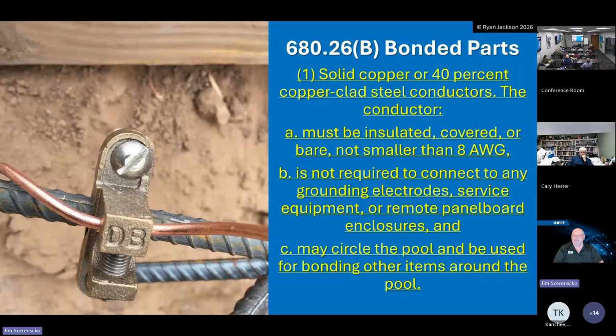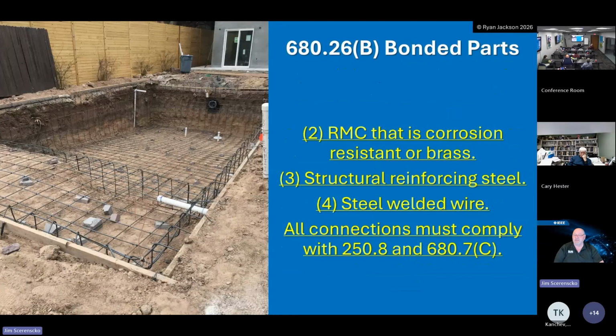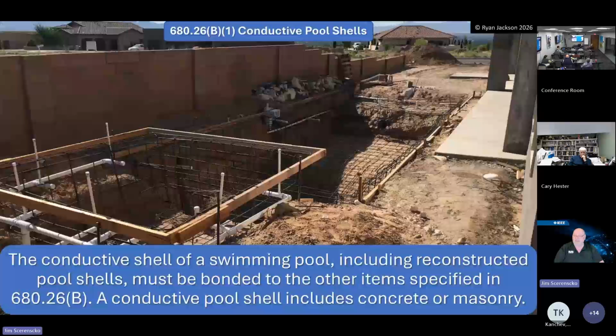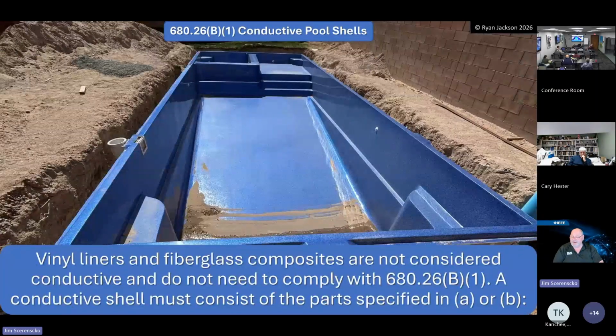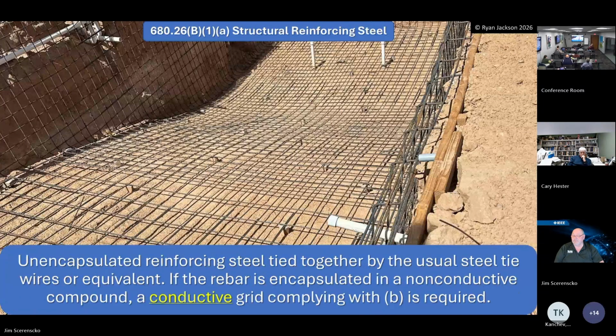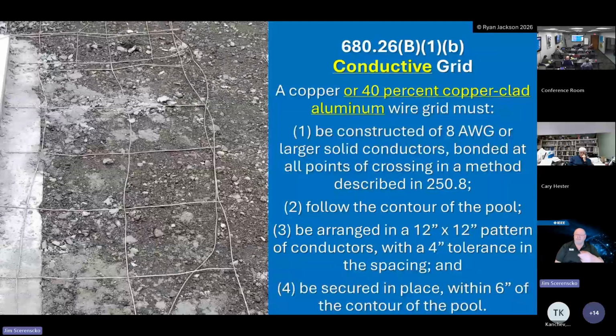We bond the cages, we bond the perimeter surfaces in a certain way. There was a change on the perimeter surface. RMC, that's corrosion resistant, or brass, can be used within 5 feet of the pool now. It never used to be allowed. Conductive swimming pools like this, that is considered bonded. It's touching the ground. Vinyl liners and fiberglass pools are not conductive swimming pool surfaces. This is, if the rebar is encapsulated, then we have to have a conductive grid under the pool, which is this.